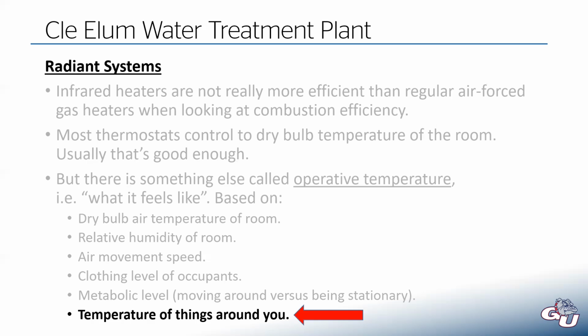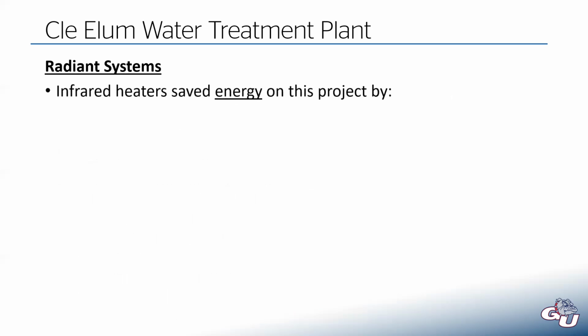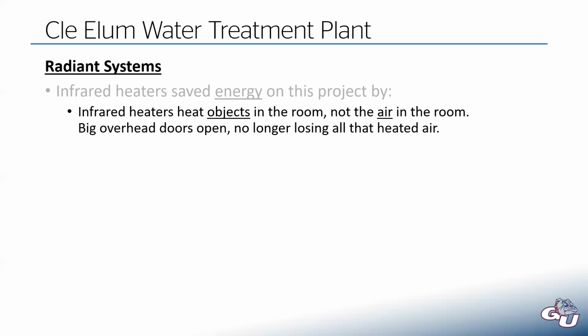And this last point, the temperature of the things around you, is the big one with regard to infrared heaters. On this project, our infrared heaters were able to save energy by essentially heating objects in the room. They are not heating the air in the room, or at least that's not their primary heat transfer mechanism. What those radiant heaters do is they're just super hot tubes in the space. They radiate all of that heat into the room, which then hits all of the objects in the room.